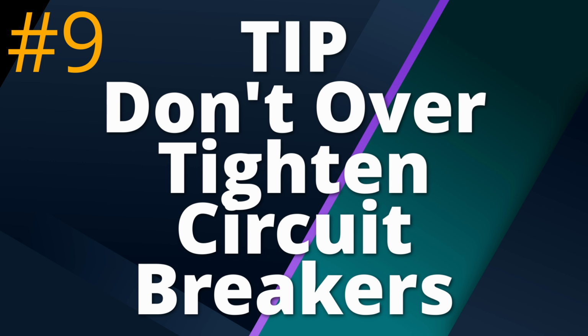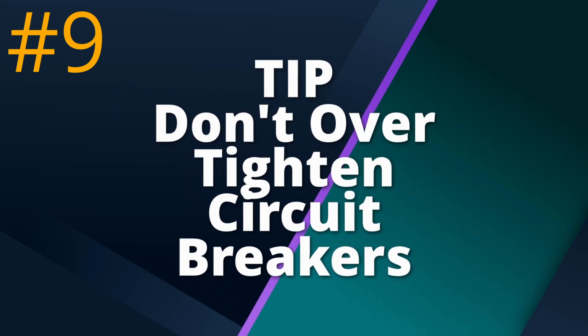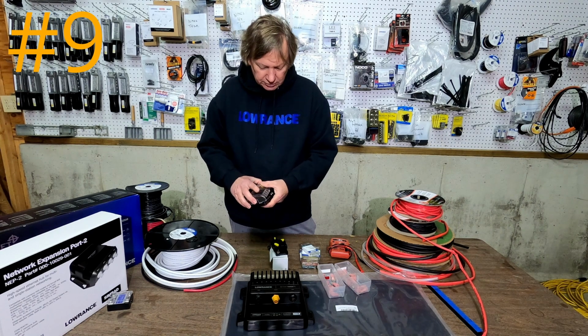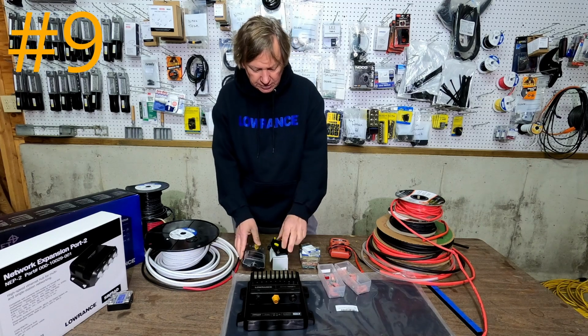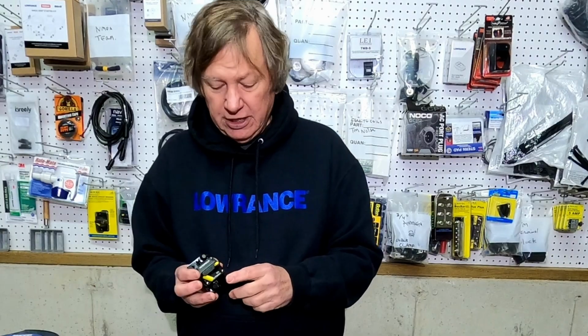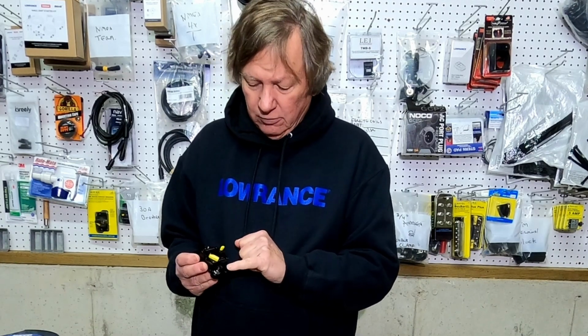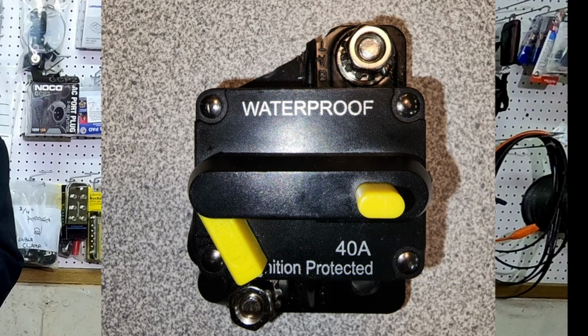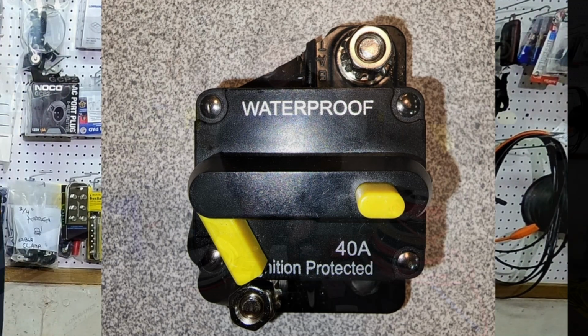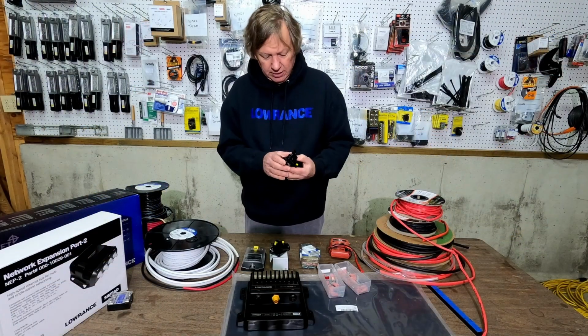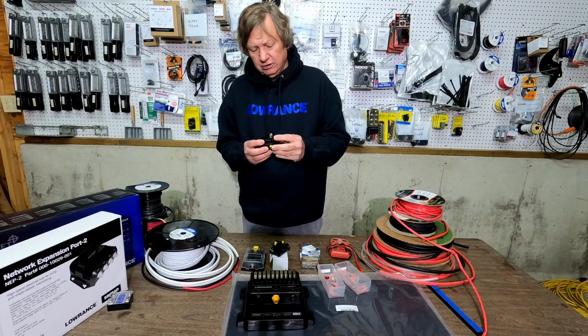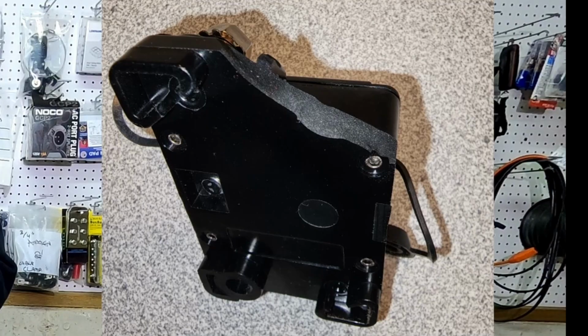This next tip is more of a caution, so you don't break components that get expensive. One little tip with these breakers: they're great, waterproof, ignition proof. But sometimes if you over tighten one of the bolts on the corner, you can actually break this thing pretty easily. Here's an example - we were trying to install it a little tight, I let the customer do it, and we just snapped the whole corner off here.